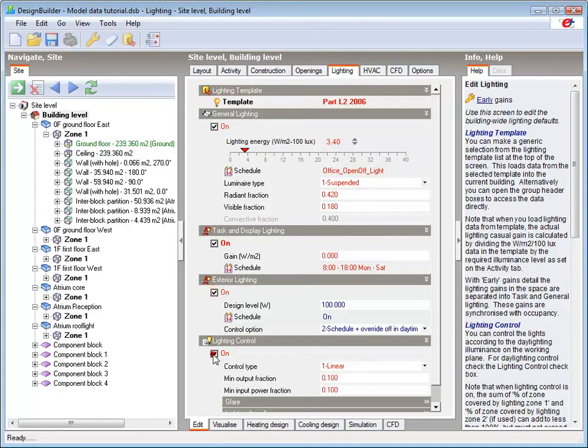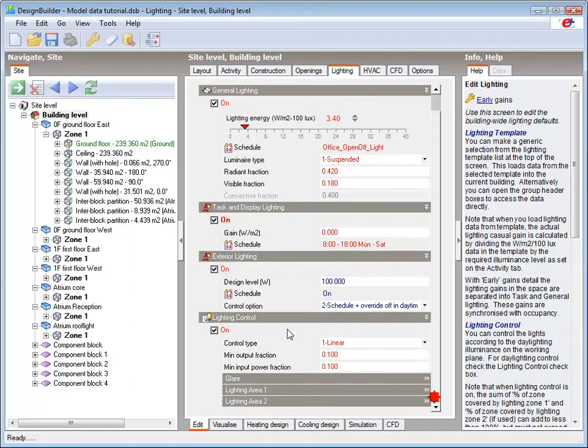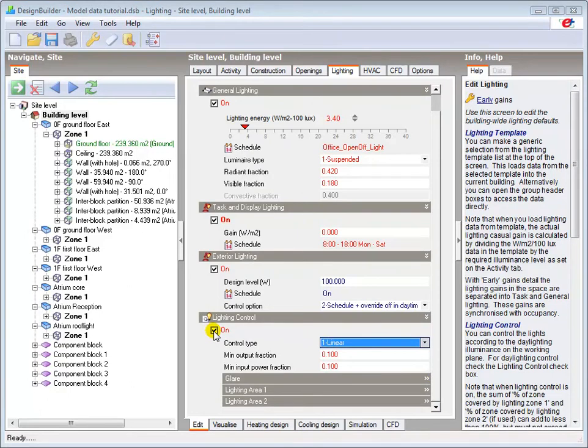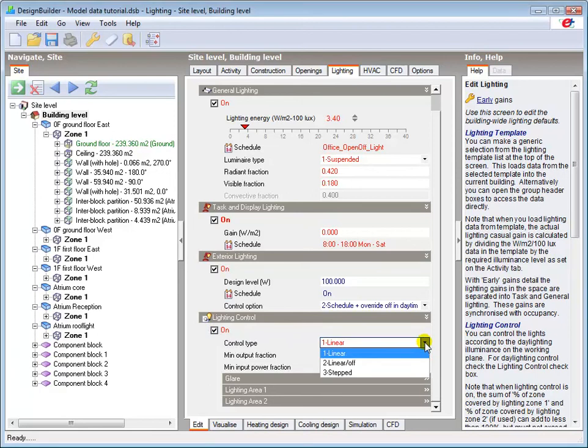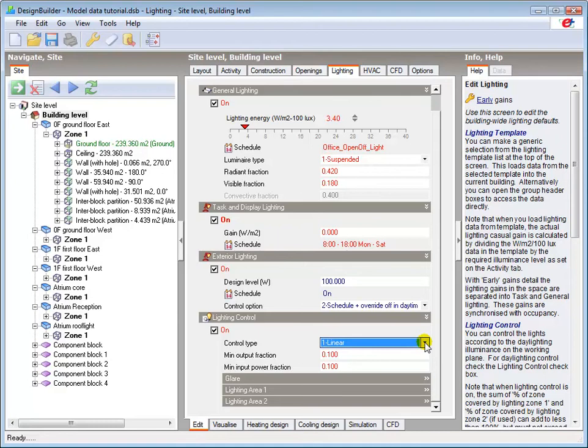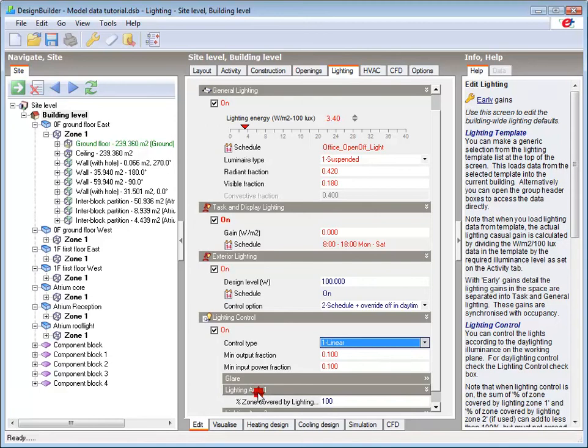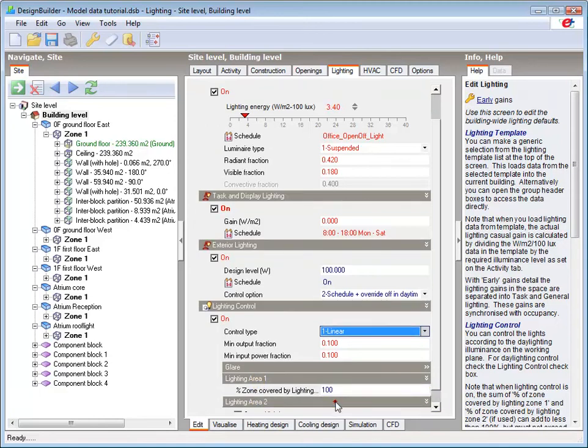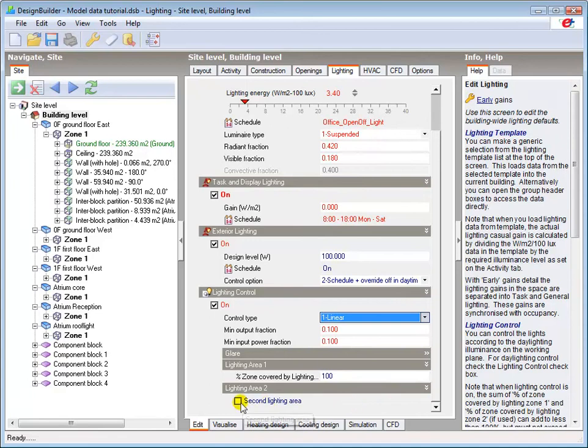The lighting control option enables you to model the reduced energy consumption and associated internal heat gains based on the use of daylight controls. These reduce the luminaire output when the illuminance on the working plane meet specified levels. The daylight simulation can be based on whether the luminaire output reduces in a linear or stepped fashion, in relation to the amount of daylight received. We can specify up to two separately controlled areas in each zone if required, such as the front and back half of the room.